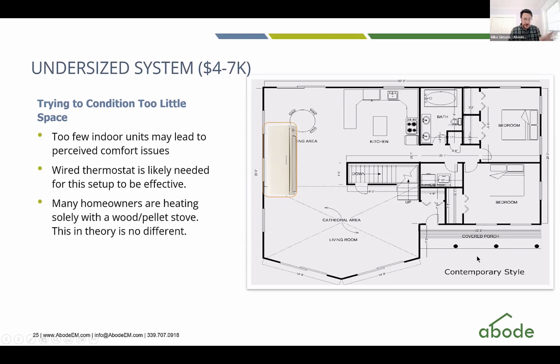So do know that you could have a heat load for this zone of 18,000 BTUs per hour. You can put in an 18,000 BTU per hour ductless mini split, and you set this thing to 72 degrees or 74 degrees. And hopefully this bedroom on the back corner is 68 degrees, and maybe this bedroom down here is 65 degrees. If someone is trying to take this approach, I do always recommend that they install a wired or a wireless thermostat to go along with this equipment. And the reason for that is if the thermostat is, say, in this bedroom and you set it to 68 degrees, this piece of equipment is going to keep running as hard as it needs to until this bedroom is 68 degrees. Without a wired or a wireless thermostat attached to it, if you just, hold on 1 second.